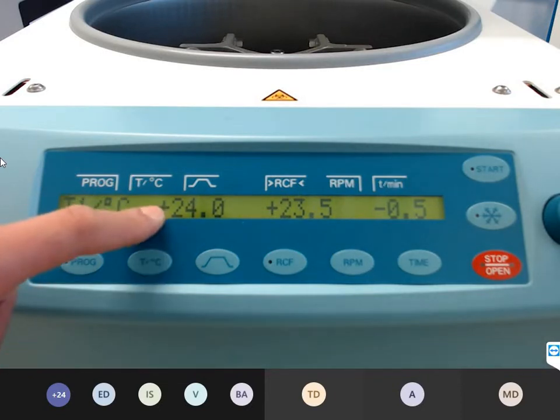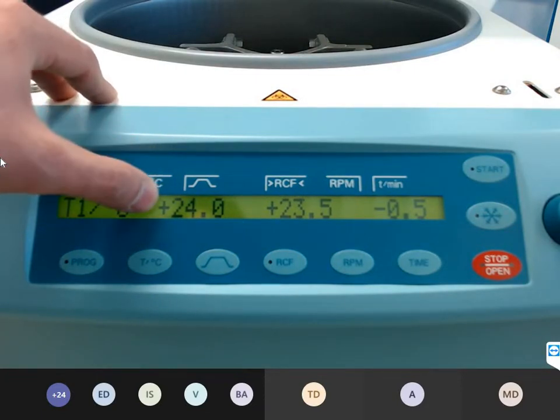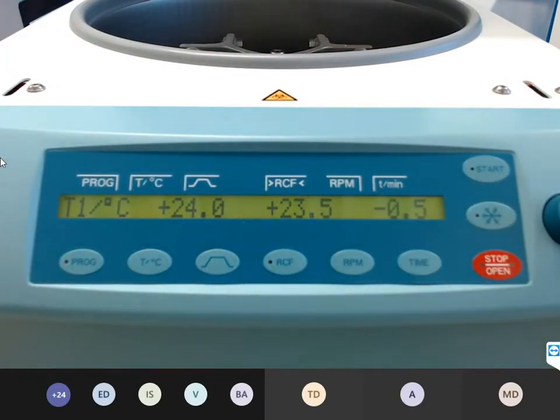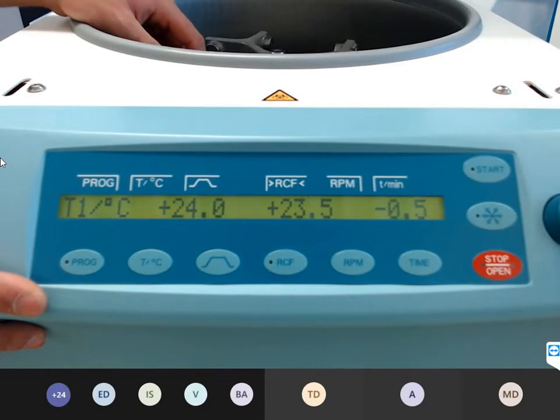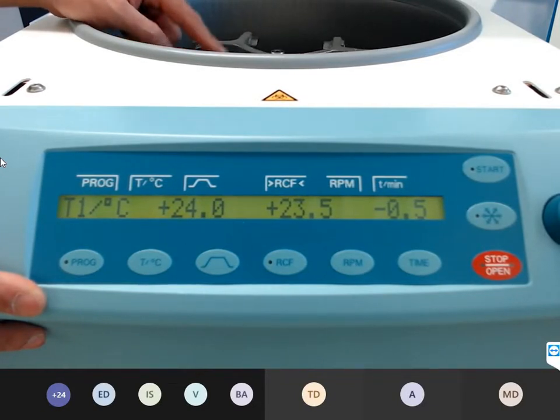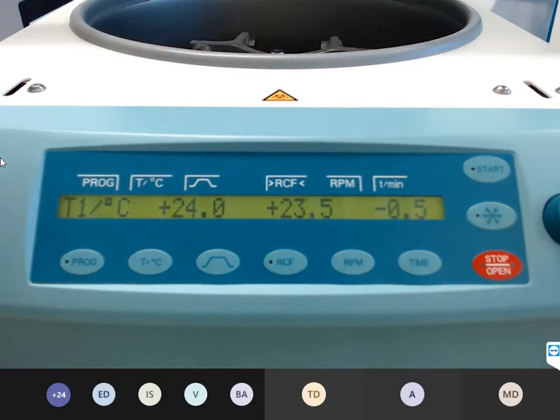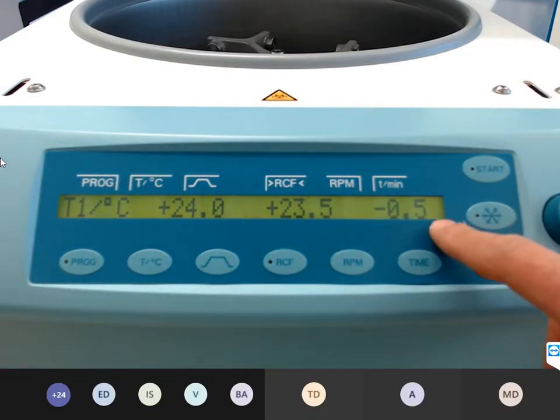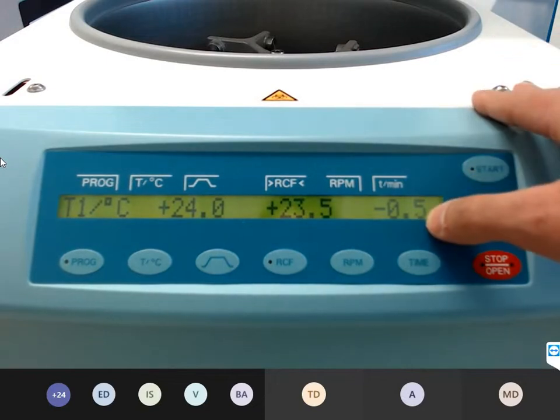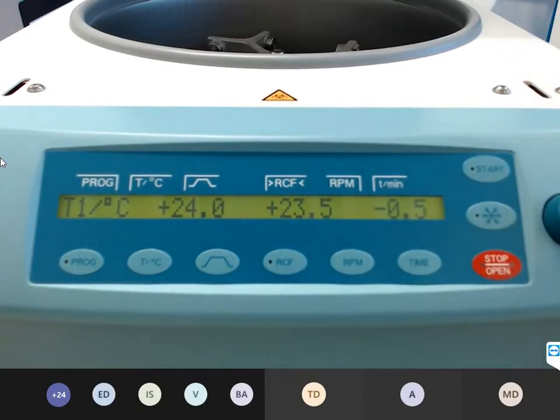For example, the first one is the temperature on the display. We set 24, and the second one is the measured temperature. How do we measure the temperature? We measure with a liquid like glycerin, make a test run, and measure it again. And this is the value between the real and the measured temperature.